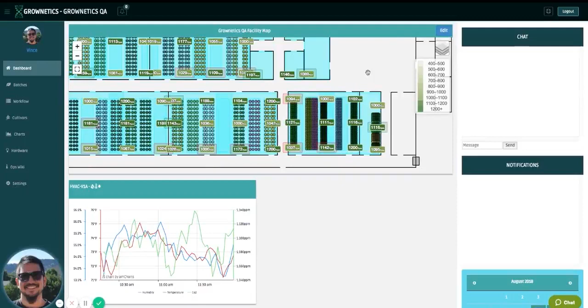In this flower room we have two HVAC zones, A and B. For HVAC A, there may be a fan coil unit above this half of the room, and we'll be driving that fan coil unit from the actual sensors closest to it. We'd be averaging the six sensors directly below it, the six arrays, and averaging between the highs and lows as well as across those locations, to drive that HVAC system to run incredibly accurately and really control the canopy environment rather than the room environment as a whole.